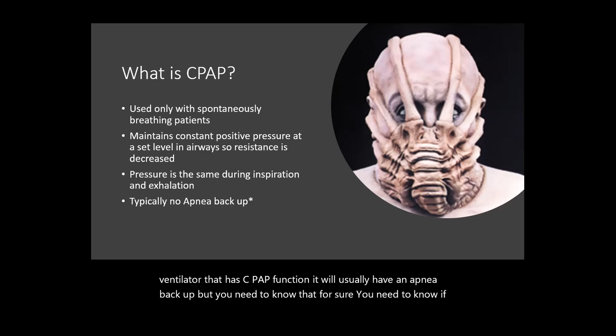Yeah, pressure's the same. PEEP is only during the end of your expiratory cycle, where this is constant pressure throughout, and it doesn't change. Now, it depends on that last little statement, typically no apnea backup. It depends on the device. If you're using a ventilator that has CPAP function, it will usually have an apnea backup, but you need to know that for sure. You need to know if it's turned on. That's where your apnea time comes in. Apnea time is the period it will allow no breath to occur before it kicks into whatever the backup mode is. In our ventilators at Ada County, it's 40 seconds, I believe, 20 or 40 seconds.